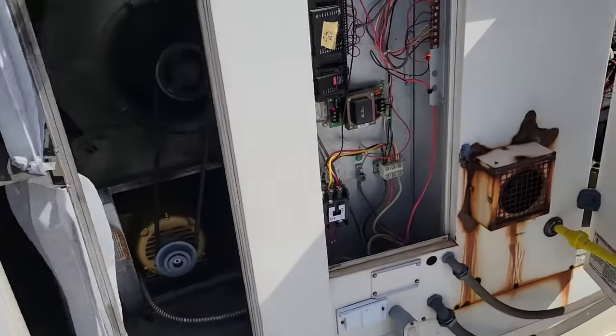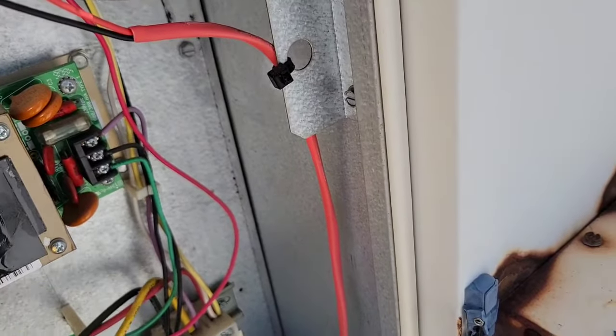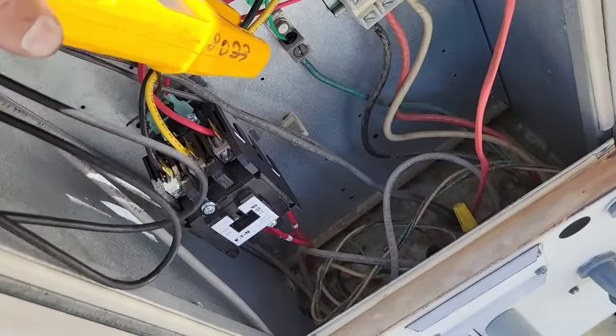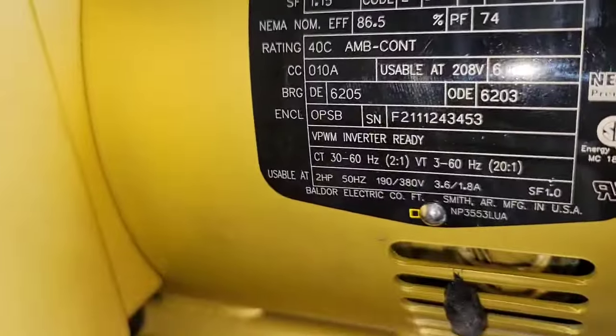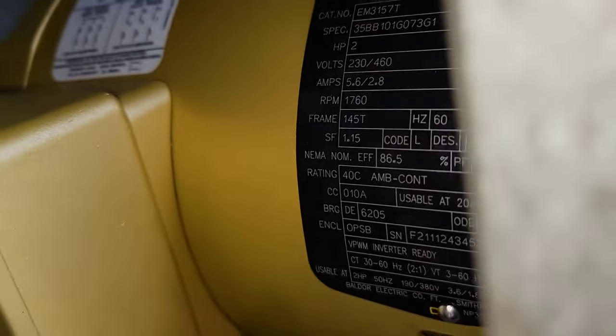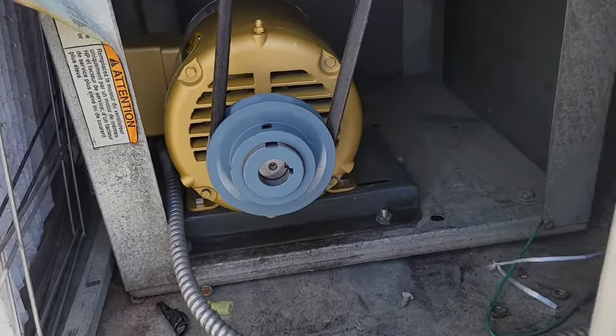So you see that's working good. We're going to come over here and take a quick amp draw. So you just saw that the amp draw was eight. If you look on the side of the nameplate, you can see that it says full load amps, and above it there's the 230 and then the 460, and underneath it it's 5.6 and 2.8. Those are the corresponding running amps that it should be drawing as it's going.